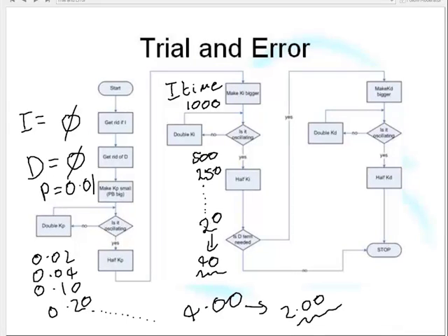Now what we've done here is we found the P and I values, because what we're trying to do, remember, is we've got these 3 boxes in our PLC called P, I, and D. So now we go to our PLC and we found 2, so we'll stick that in for the P. We found 40, we'll stick that in for the I. Now, in almost every circumstance, we would just leave the D alone and just stick a 0 in for the D. But if you're crazy and you want to stick a D in, then you do the same as you did for the I. You start with a big value and you work down.